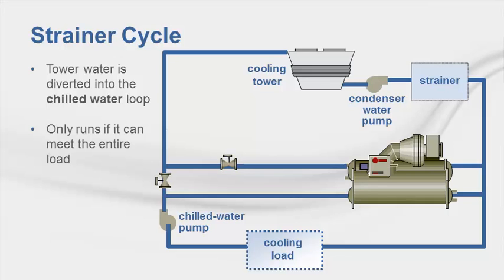Typically, the tower water passes through a filter or strainer before entering the chilled water loop, hence the name. The strainer cycle cannot run simultaneously with the chiller, so if the tower cannot meet the entire cooling load, the strainer cycle does not operate. This is not used much, but sometimes an existing system must be modeled for comparison purposes.